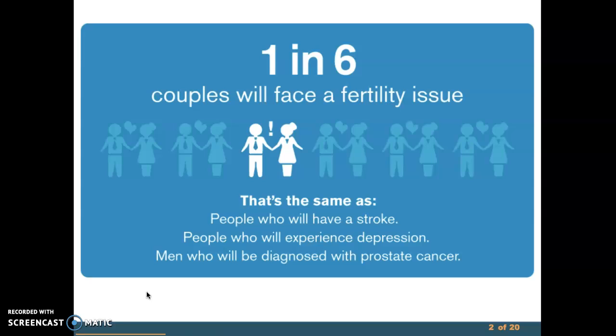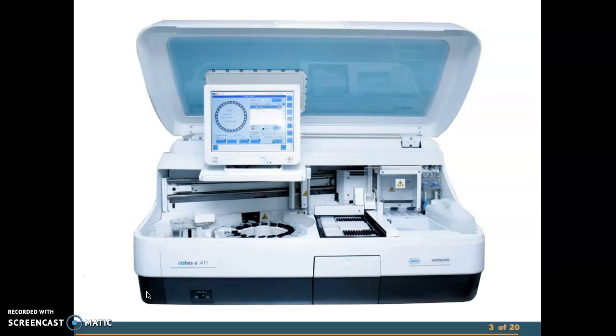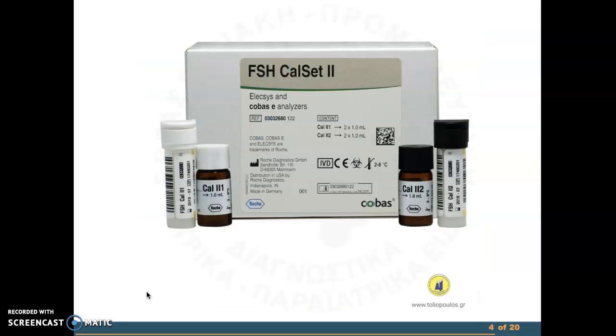When using a Cobas E411 to measure hormone levels in patients' blood serum, there are a number of steps we must take to ensure results are accurate representations of the treatments they are undergoing. In order to ensure accurate patient results, we need to make sure the machine is calibrated correctly and passing quality control standards, that the blood we are receiving is labeled correctly and corresponds to orders for blood to be run on our machine, and that the results that come off the machine once it is done processing are accurate representations of the patient's treatment plan and are in the range we expect them to be based on previous results.